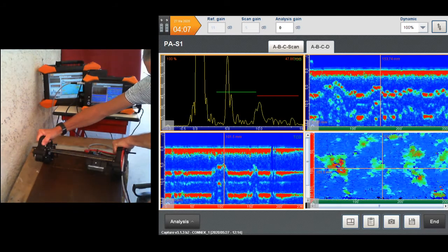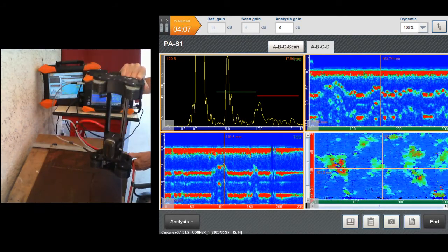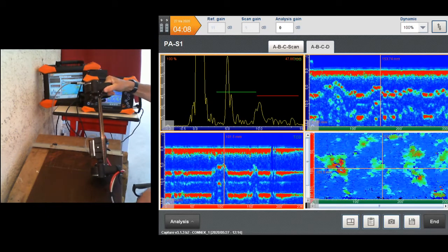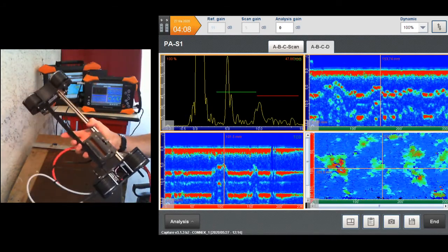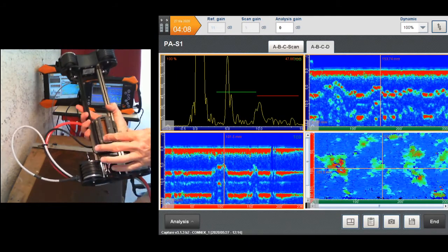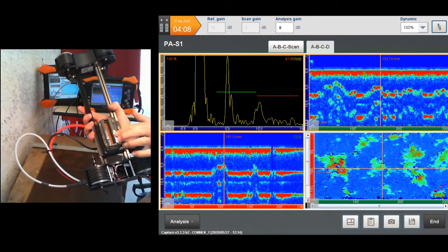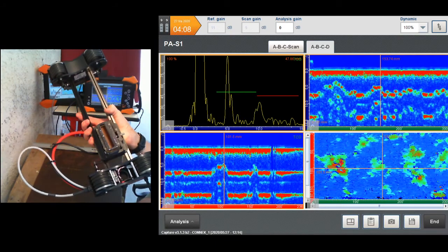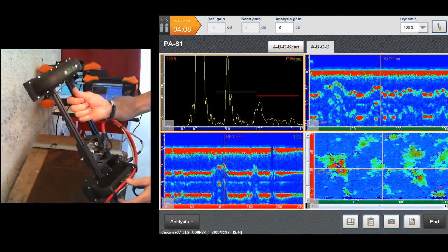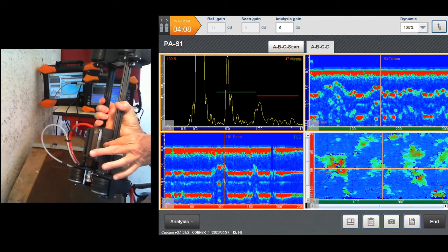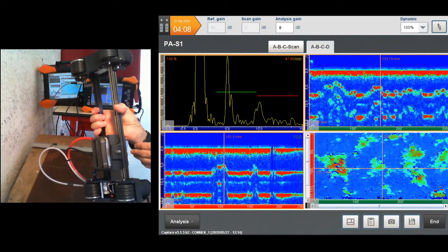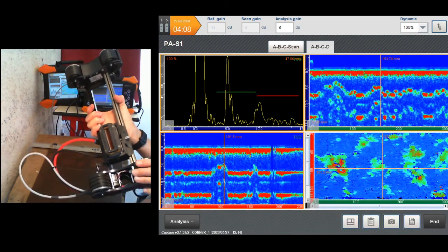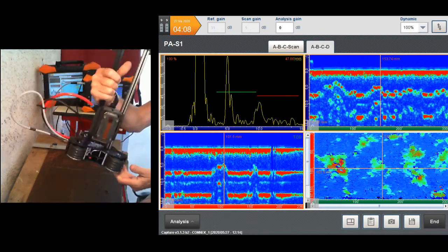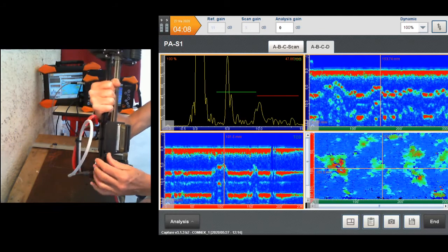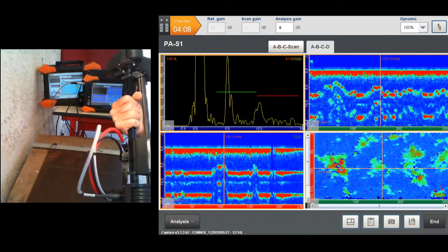On that, at first I have a scanner, so I can show you the Connex mapping scanner. It's a new scanner that is going to be launched. This one can embed the Aqualock. We have the foam so that we can keep water inside. From the top here we have a phased array probe, and we can just unscrew this and remove the probe to remove the Aqualock. Quite easy. We have magnetic wheels, and here we have a brake on both wheels, very easy to lock.